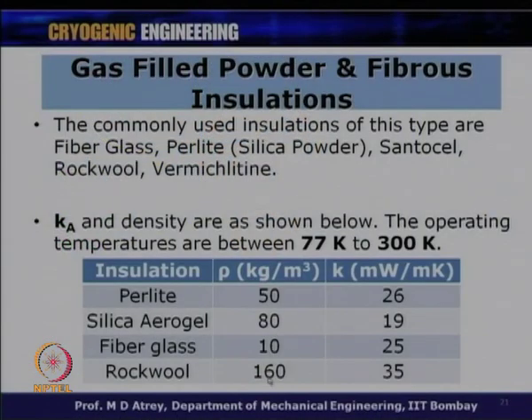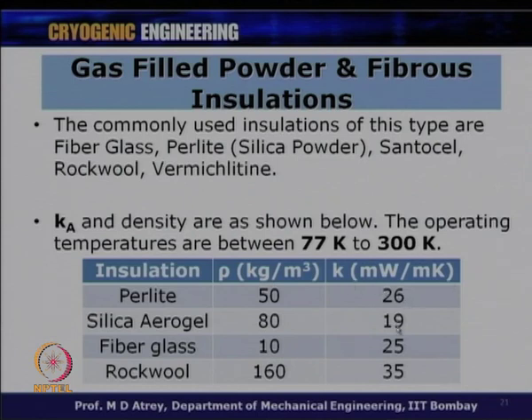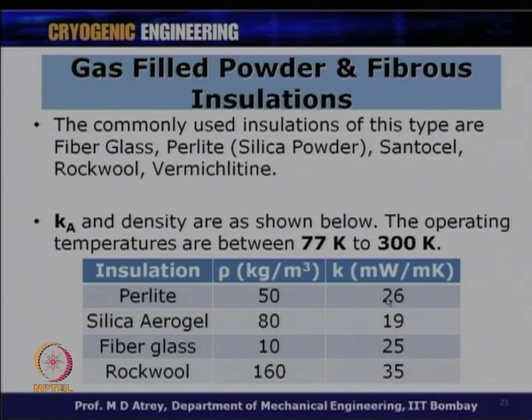The apparent thermal conductivity Ka and density for powder and fibrous insulations at 77 K to 300 K are: perlite powder Ka ≈ 26 mW/m·K; silica aerogel Ka ≈ 19 mW/m·K; fiberglass (density ~10 kg/m³) Ka ≈ 25 mW/m·K; rockwool (density ~160 kg/m³) Ka ≈ 35 mW/m·K. Compared to expanded foam (30–60 mW/m·K range), the gas-filled powder range is around 20–35 mW/m·K — a notable improvement.